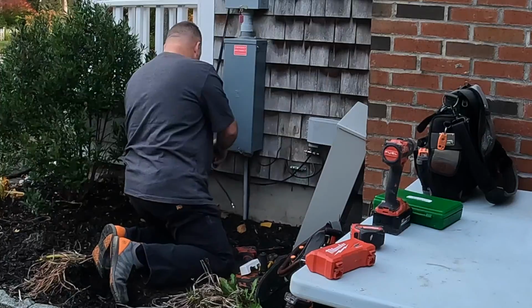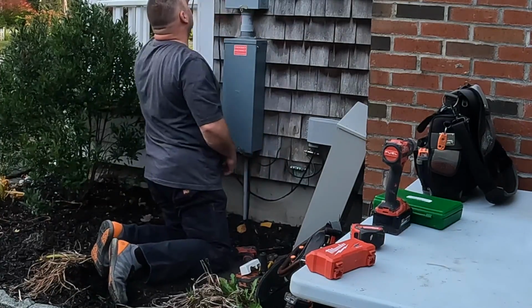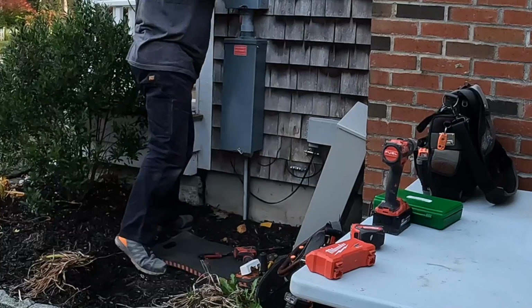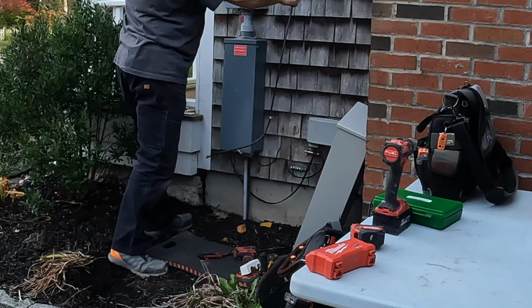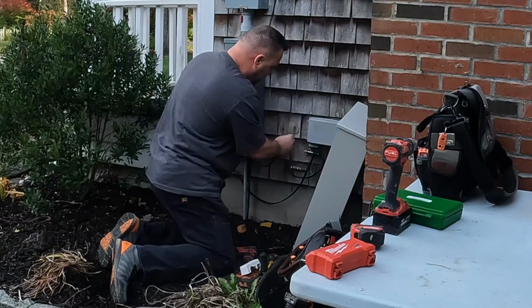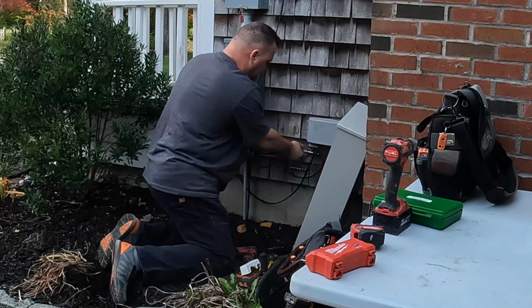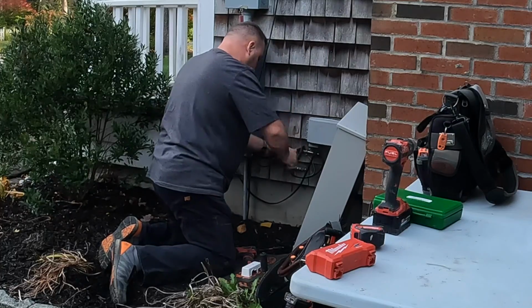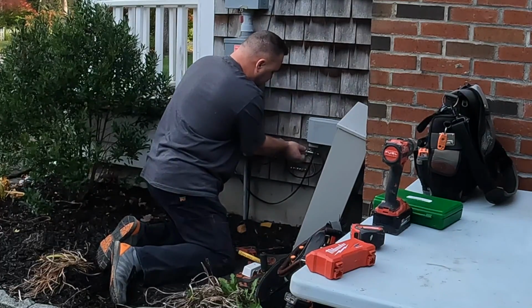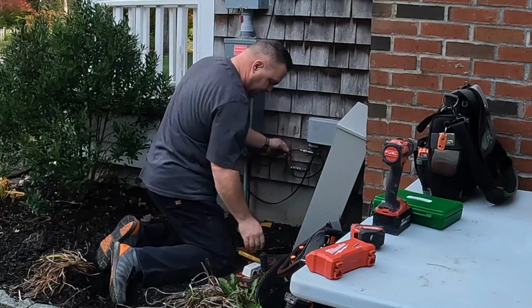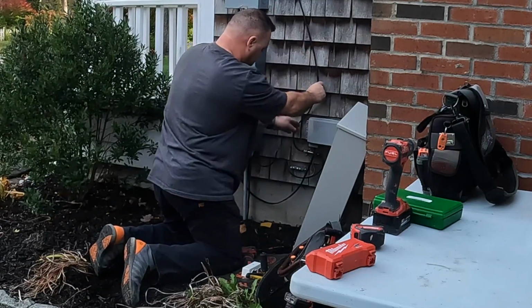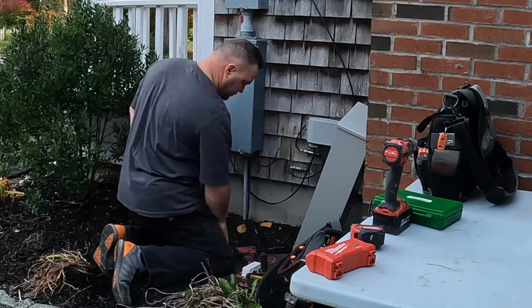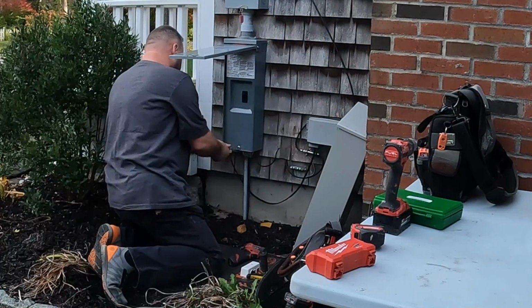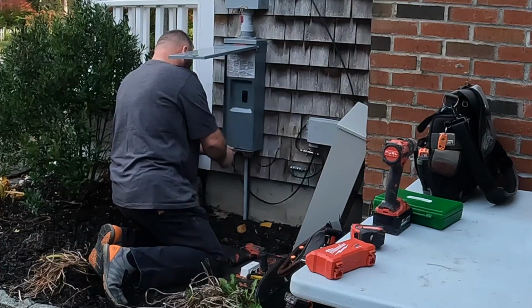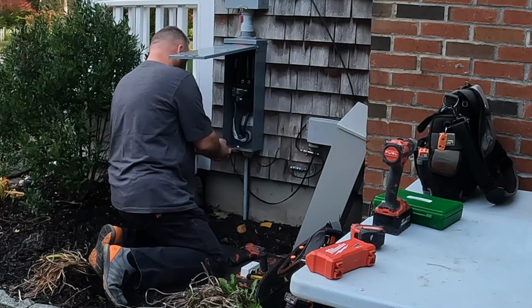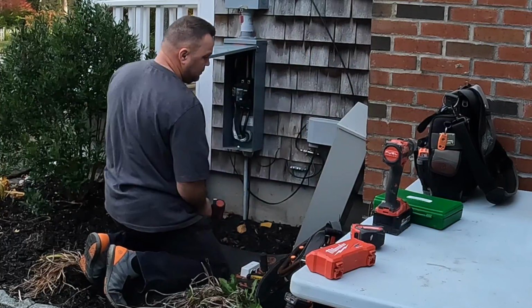If the utility's grounded neutral conductor becomes undone, the electrons still find a path back to the source through the grounding electrode conductors and the grounding electrodes that are installed as part of the grounding system. This is an example of why it's so important to fully understand your grounding and bonding when you're going to be doing electrical work, especially on the service here. If you don't understand those principles, then if that system neutral is busted and you touch this grounding electrode conductor, you become a part of the path of the entire current flowing through that house. And you could very well be dead as a result of that.